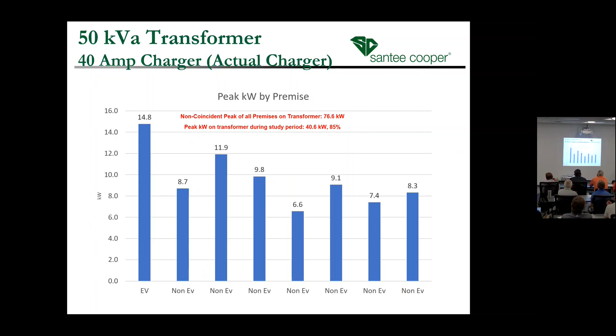So we took all of our customers and asked, what size transformers do they have? We ran a report of all our customers using our rebate program and found about 11% are on 25 kVA transformers. Those are probably the ones we should look at first. So that'll likely be our next step - look at those customers, understand their usage, make sure they're not currently overloading those transformers too much, then move on to the 50Ks, and eventually get to the 75 and 100 kVAs. So, what are we doing to deal with demand?